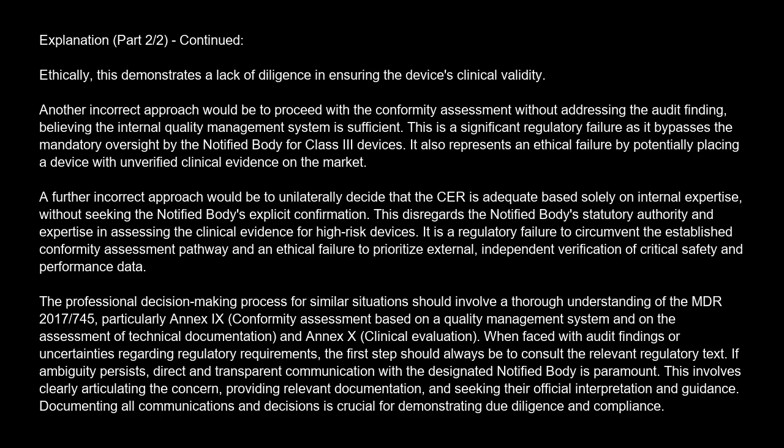A further incorrect approach would be to unilaterally decide that the CER is adequate based solely on internal expertise, without seeking the notified body's explicit confirmation. This disregards the notified body's statutory authority and expertise in assessing the clinical evidence for high-risk devices. It is a regulatory failure to circumvent the established conformity assessment pathway and an ethical failure to prioritize external, independent verification of critical safety and performance data.